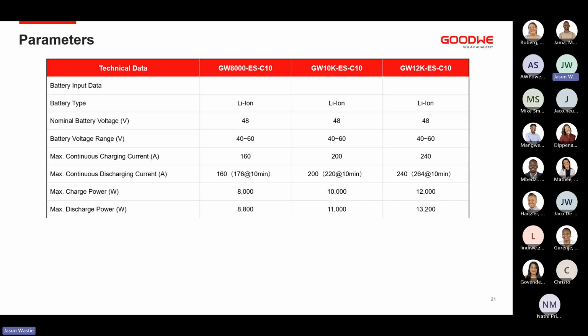The max discharge being the same, but if the battery current discharge value is higher than the inverter, it will allow for around 10% extra for up to 10 minutes. The max charge power is 8, 10, 12 kilowatts, and the discharge at 10% more than capacity, so you'll get 13.2 kilowatts off your 12 kilowatts.